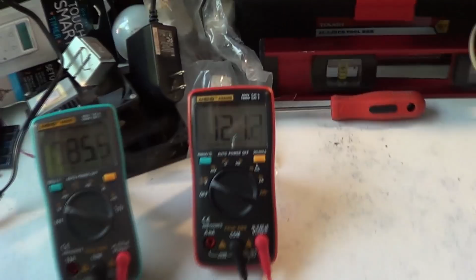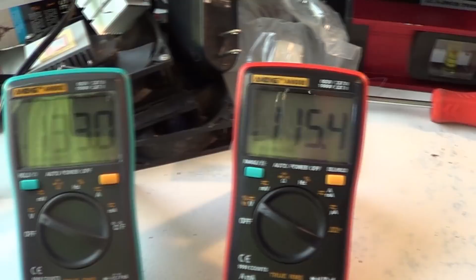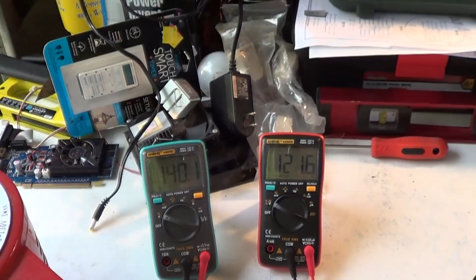Now we'll start cranking the voltage up here. That light bulb gets pretty bright. Then there's another relay click, and a different winding within this thing's auto transformer is switched in. You can see we have high line voltage over here, 139 volts AC and 115.4 volts AC coming out of the UPS. And if I keep going, if I keep pushing it, it'll compensate for as long as it can, and then it'll give up and switch to battery.